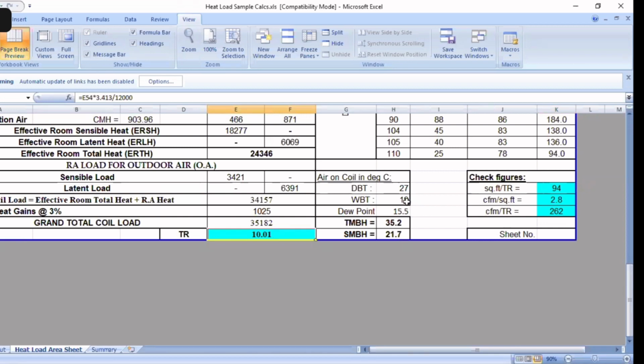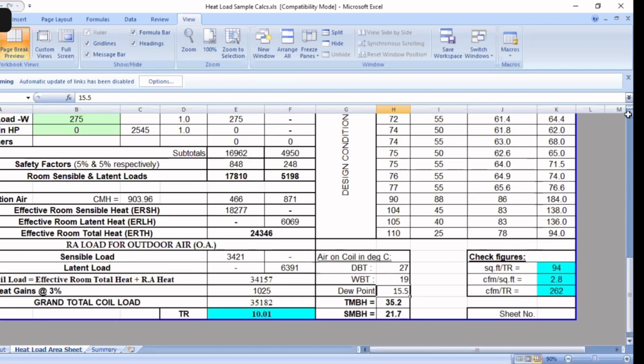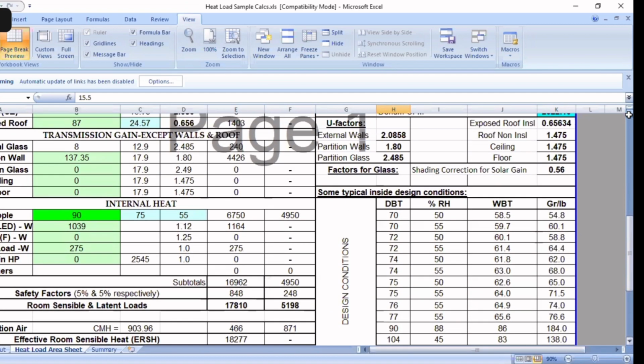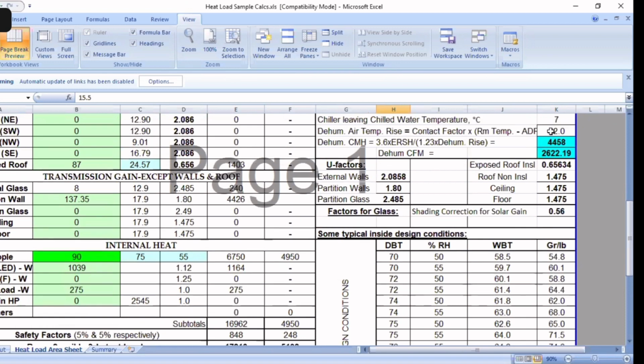And here the dew point of the return air is also calculated. It is 15.5 degrees centigrade. I have set my cooling coil apparatus dew point as 12 degrees centigrade, so it is lower than the dew point of the return air. So there will be enough condensation and room latent heat will be taken out properly.